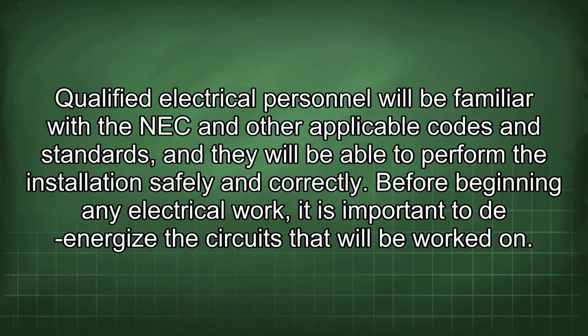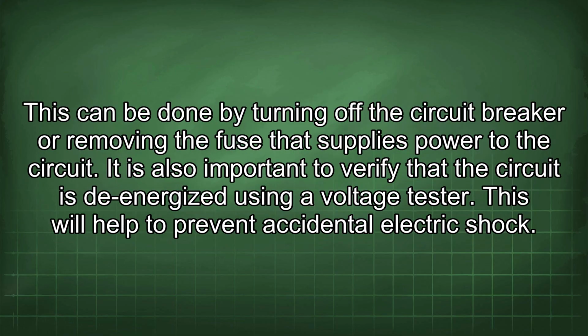Before beginning any electrical work, it is important to de-energize the circuits that will be worked on. This can be done by turning off the circuit breaker or removing the fuse that supplies power to the circuit. It is also important to verify that the circuit is de-energized using a voltage tester. This will help to prevent accidental electric shock.